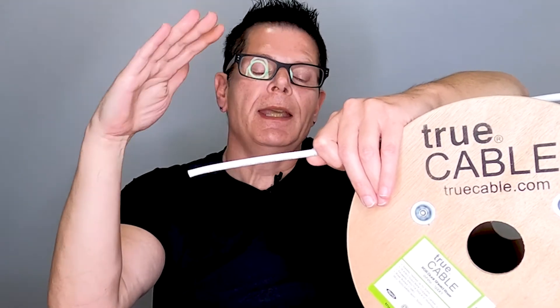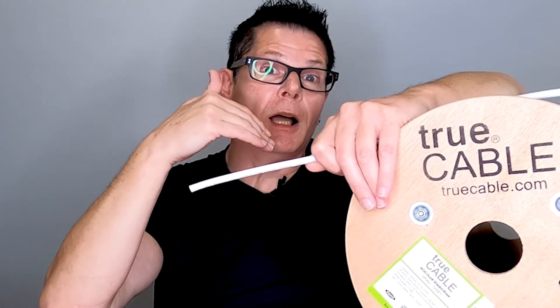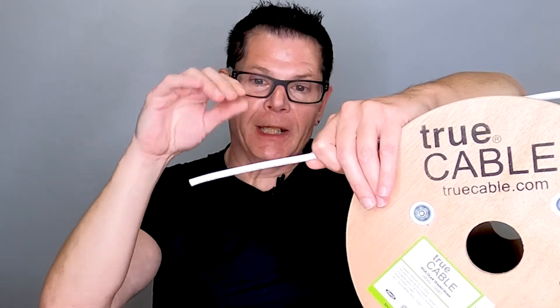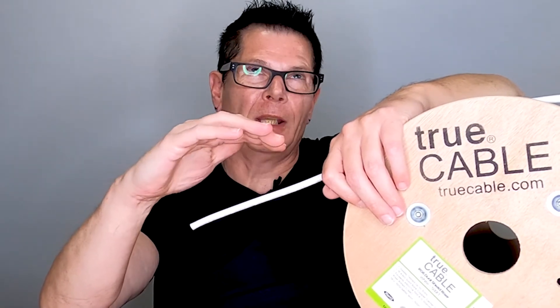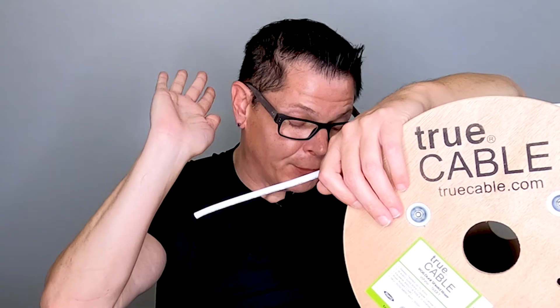It's the perfect cable if you don't have a high EMI/RFI environment. In other words, if you're running it and you can maintain an eight inch separation from 120 or 240 volt AC, then treat it just like you would unshielded ethernet cable. You can think of dual shield coax as the equivalent of unshielded ethernet in regards to EMI immunity.